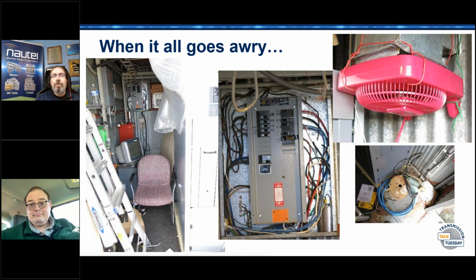That's not a bad question, Keith, and the answer is it depends. If, for example, you were in Willis Tower, which will always be Sears Tower, sorry Chicago folks, or the Empire or IDS or any of the big buildings, typically the frame of the building is the reference ground. Others will have dedicated grounds run to each transmitter room with a bulkhead panel to connect to. If you're on, say, the upper floor of a two-story building, then in that case you probably should have a dedicated ground run from earth to the room, and downstairs where the electrical entrance comes into the building, that should be tied to the electrical entrance ground.